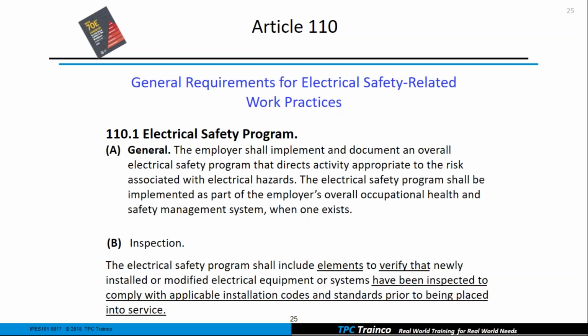You could have an engineering team and they could come out and inspect it themselves. That could be an outside entity. You could have an electrical inspector come in and inspect that. Or you could even have maybe the manufacturer of the equipment come and see if it was installed correctly. So it just has to be something that is documented and somebody has said, yes, this is good to go. We can now energize and make this happen.